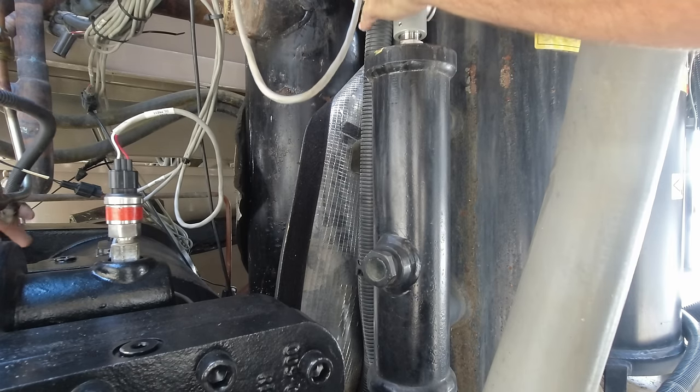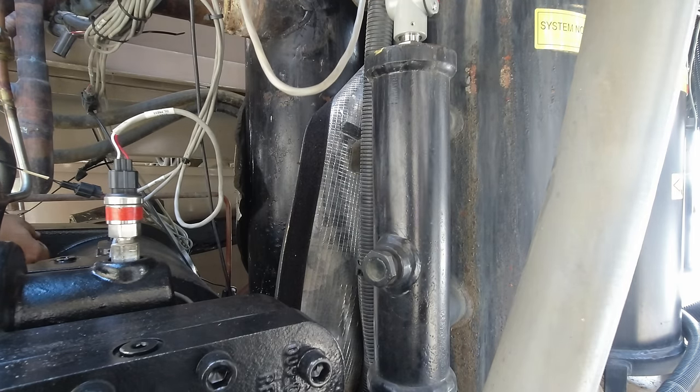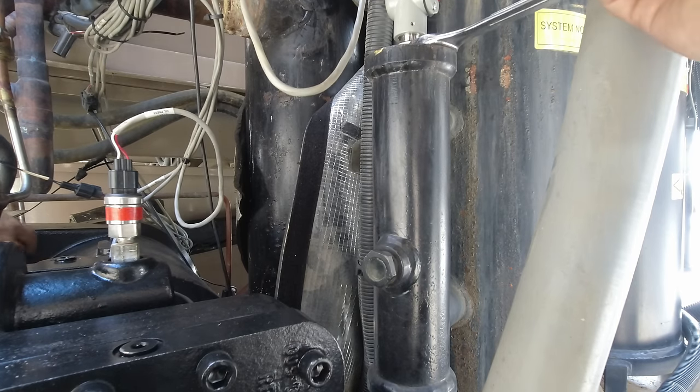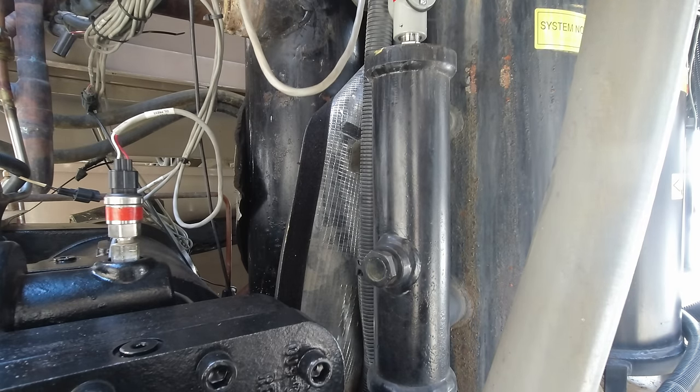Don't use Teflon on refrigerant. I think they make some refrigerant-safe sealants out there. My personal choice is Nylog, just across the board. Another option, while not my personal preference, would be Loctite 515 if you needed an alternative. The common industry standard is 515.